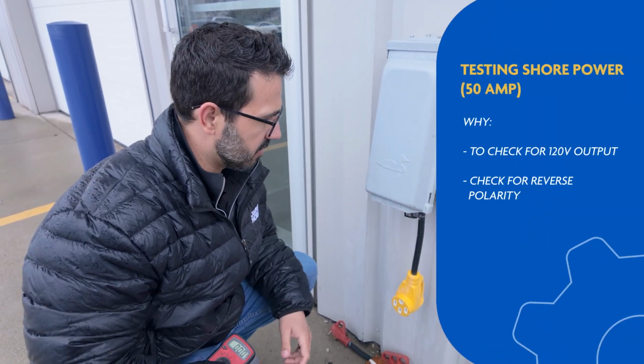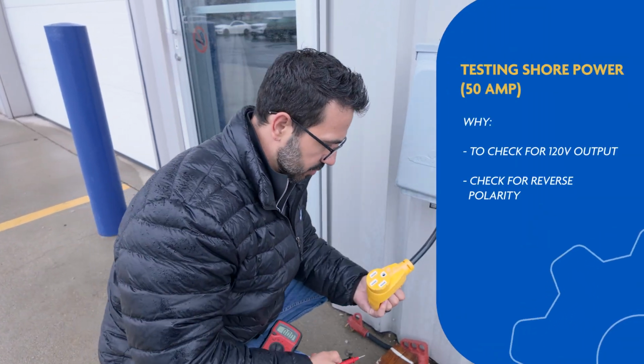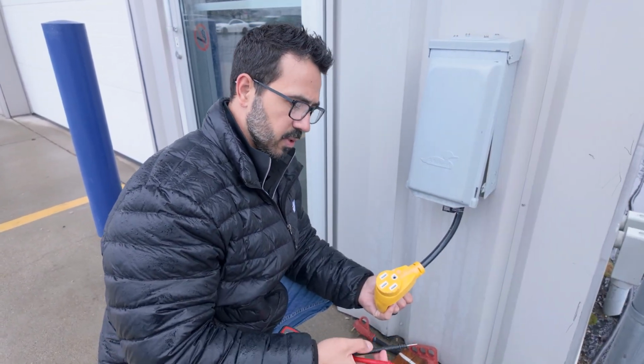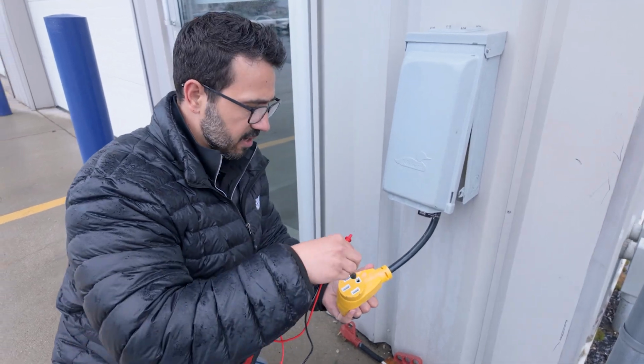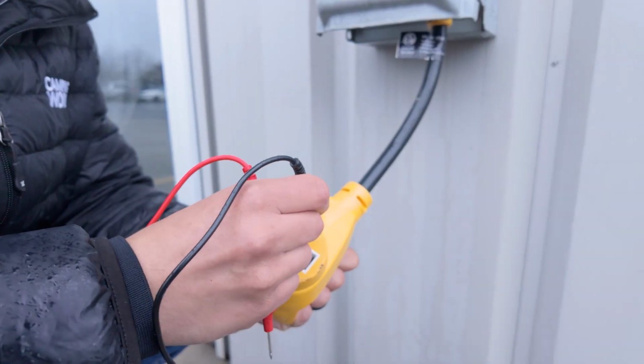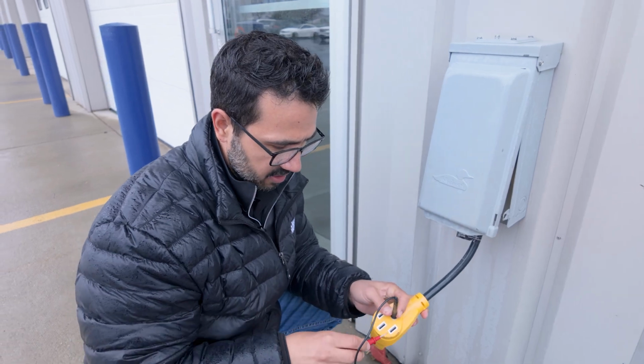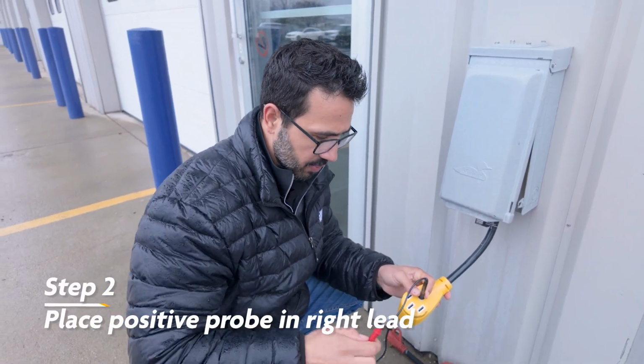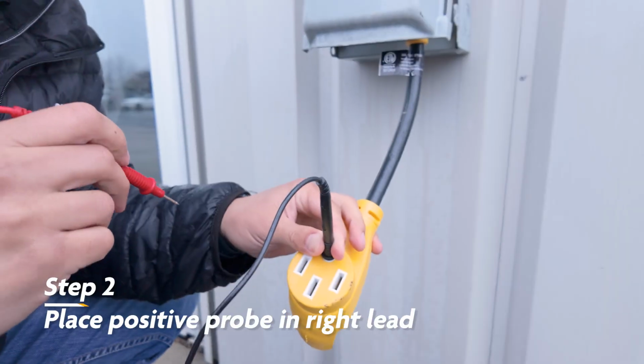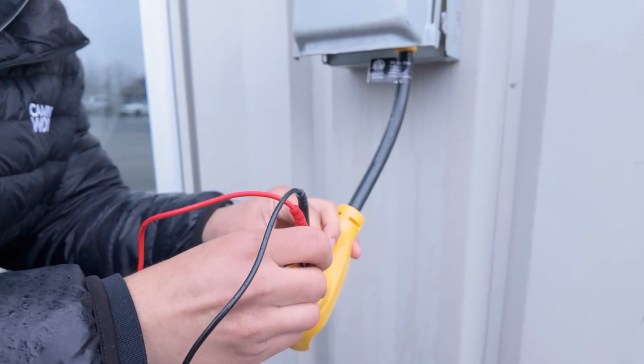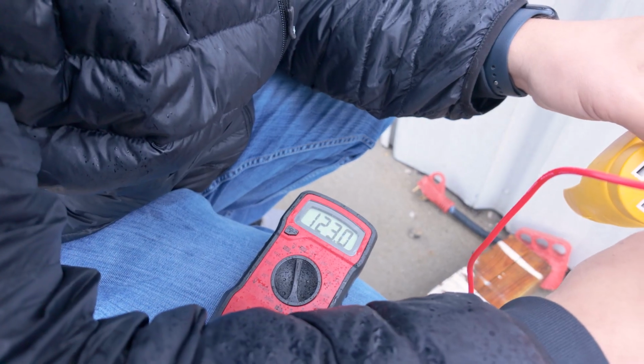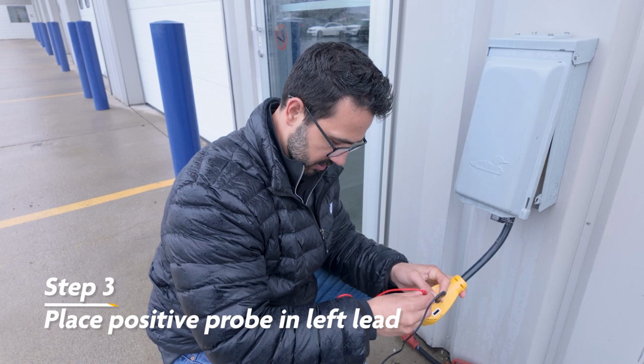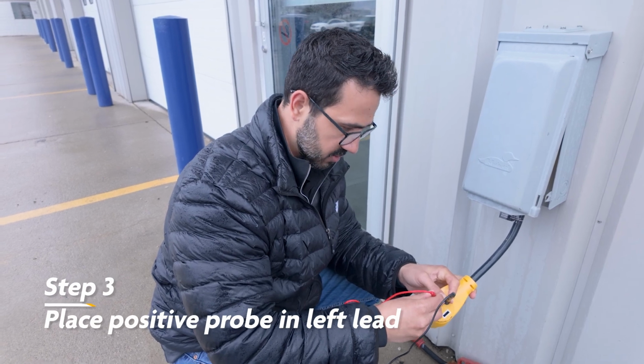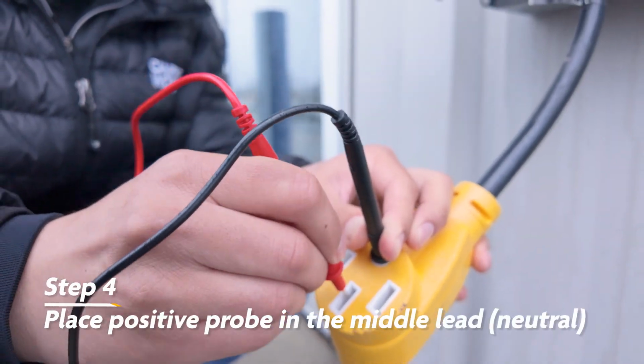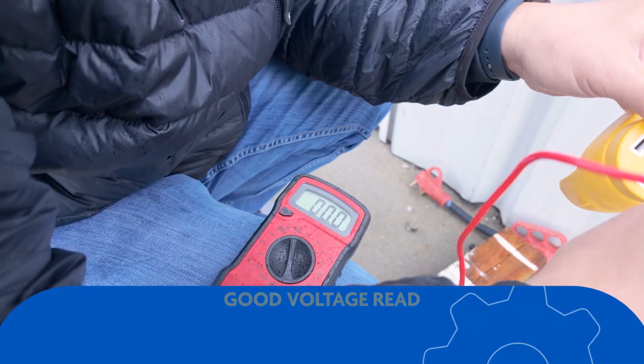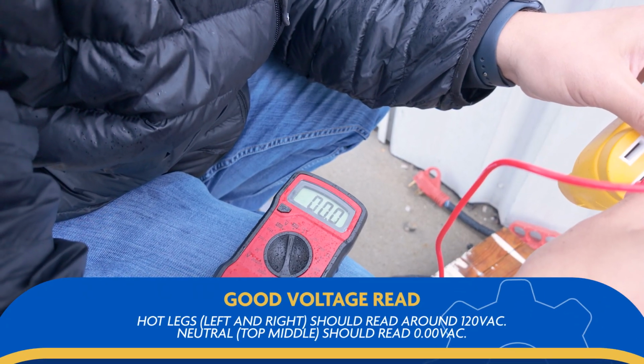Well, I don't have a 50 amp here, but I'll use a dog bone just to kind of show you. It's the same basic principle. What we're going to want to do is take our negative probe here. We will place that in the ground, and then we'll take our positive and put it in either leg. We're going to put it in both, but we want to check them individually. So we'll put it in one, kind of wiggle it around till we get it. There we are. Once we know that one's good, we will switch over to the other one. Perfect. Once we see that one is good, we will then put it in the neutral, and it should read all zeros. And that's that.